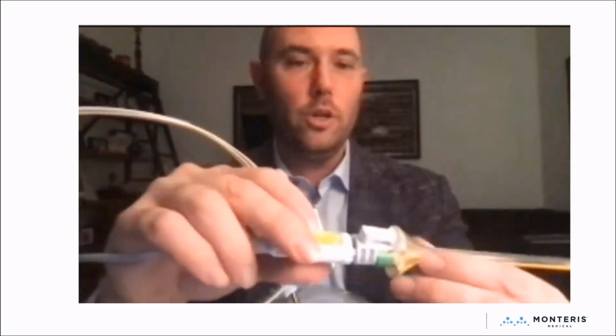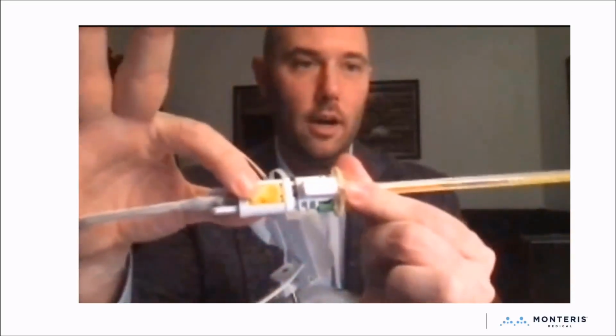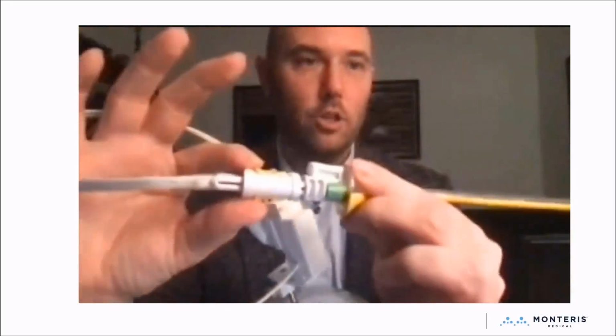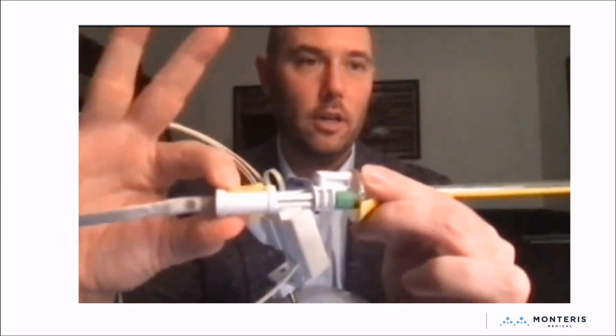But basically what you want to do here is look at your laser catheter, and you'll have taken your stick and touched it to the lip of the bolt at some point and figured out your depth to target. And now with this new fancy yellow laser ruler, you'll be able to just put that number in. So if you figure out that your depth to target is 95, for instance, then you're going to adjust that. There's a little yellow clicker button here on the back, and it's two sides. So you're going to squeeze it between two fingers. You'll hear it click, and now I can move the laser in and out of the ruler.